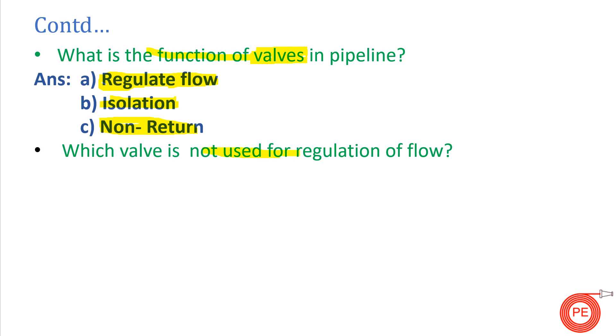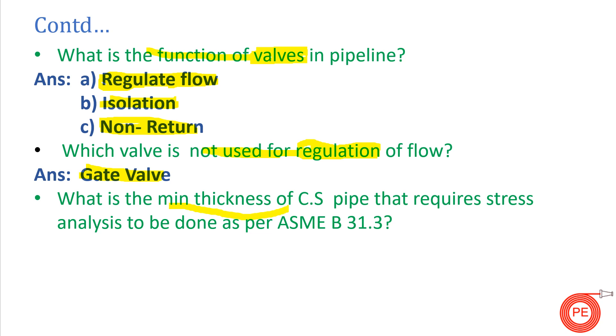The next question is: which valve is not used for regulation or throttling? The gate valve is not used for regulation. If someone asks which valve is used for regulation, the answer is either a butterfly valve or a globe valve — also known as a control valve. Both butterfly and globe/control valves serve the purpose of throttling or regulation.